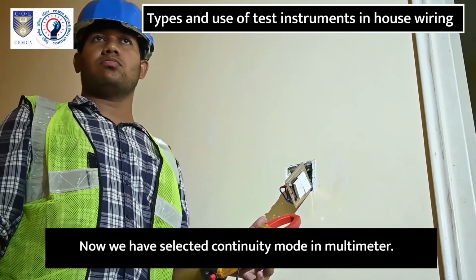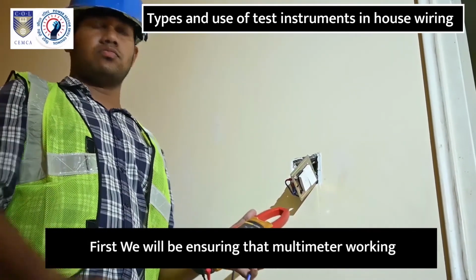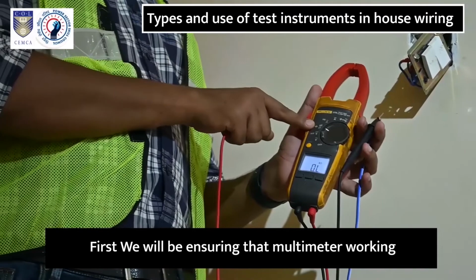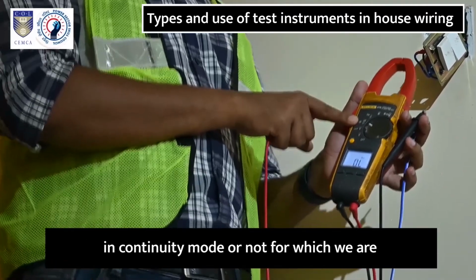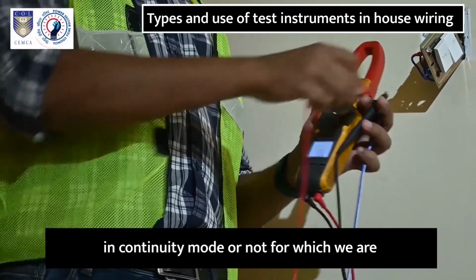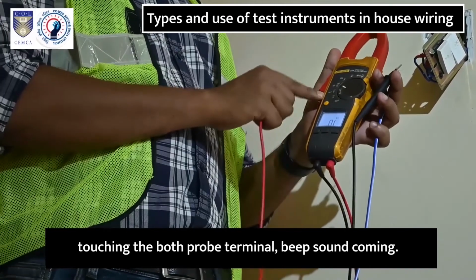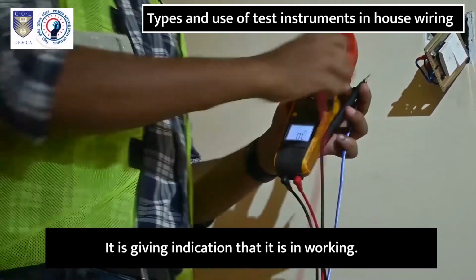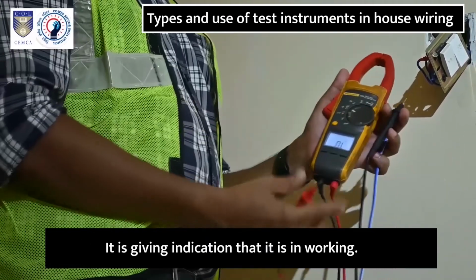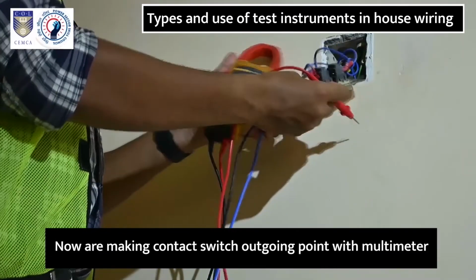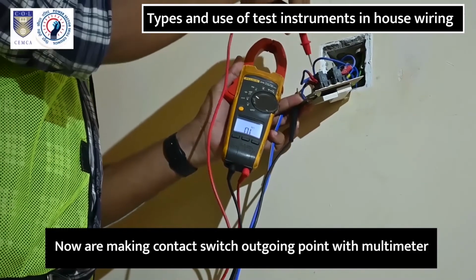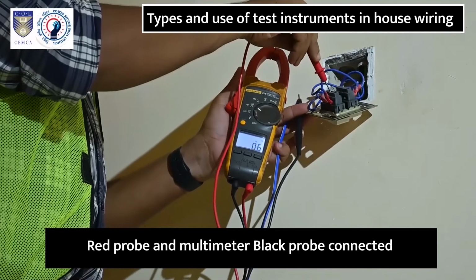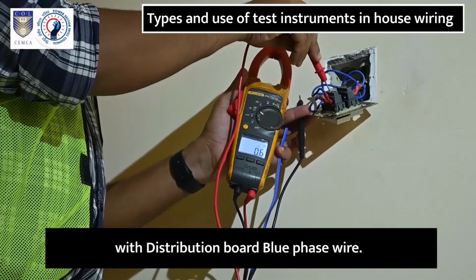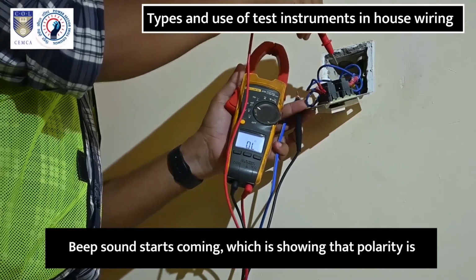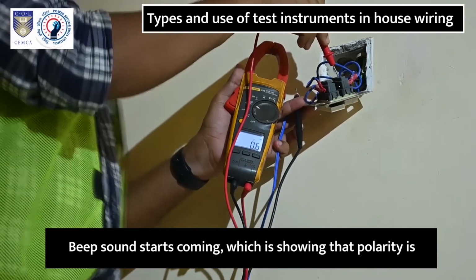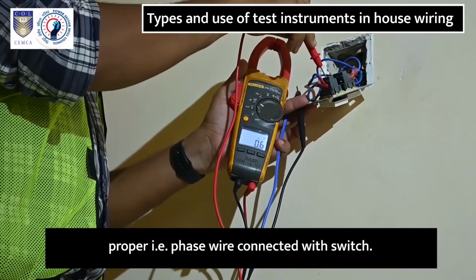Now we have selected continuity mode in multimeter. First we will ensure that the multimeter is working in continuity mode or not, for which we are touching both probe terminals. Beep sound is coming. It is giving indication that it is working. Now we are making contact of the switch outgoing point with the multimeter red probe and the multimeter black probe is connected with the distribution board blue phase wire. Beep sound starts coming, which is showing that polarity is proper, that is phase wire is connected with the switch.